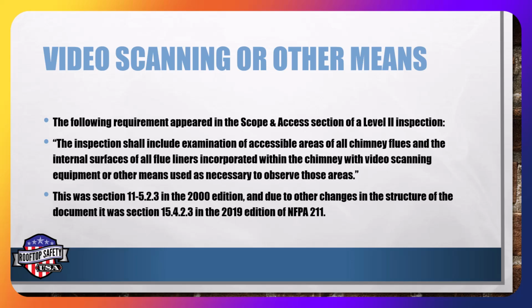And the section in question read, "The inspection shall include examination of accessible areas of all chimney flues and the internal surfaces of all flue liners incorporated within the chimney with video scanning equipment or other means used as necessary to observe those areas."